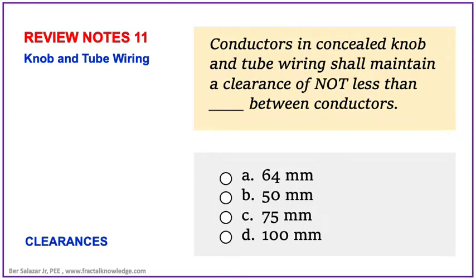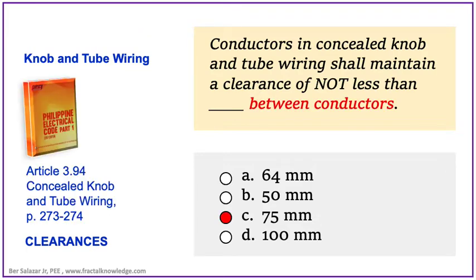Another example problem related to concealed knob and tube wiring asks: what is the clearance between conductors that shall be maintained? The answer can be found in 2017 PEC Article 3.94, page 274. The correct answer is 75 mm clearance between conductors.